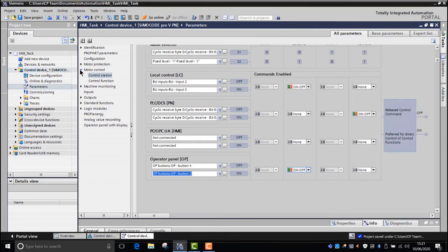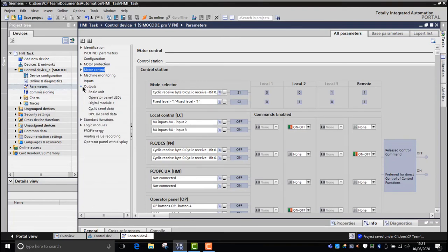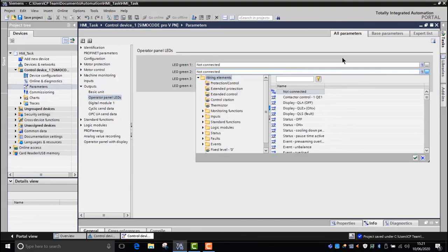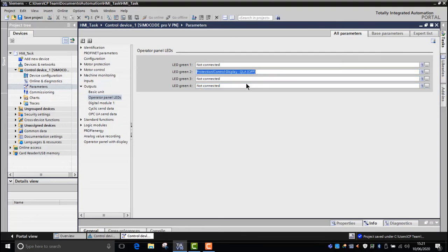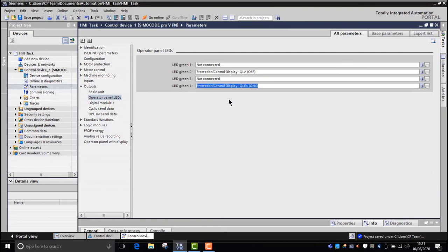So in outputs, we now have the operator panel which has been added in here. Select operator panel, go to the dotted line on the LED for green output 2. That needs to be assigned for the off command. And for the stop push button, we want the green light to come on, so that's the on command. Select that.